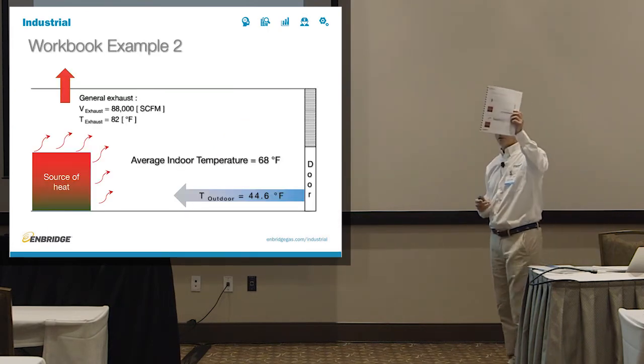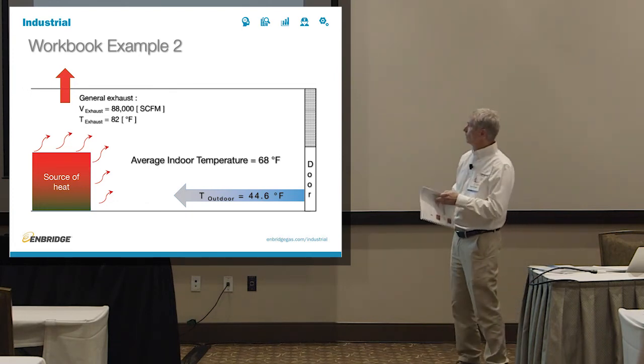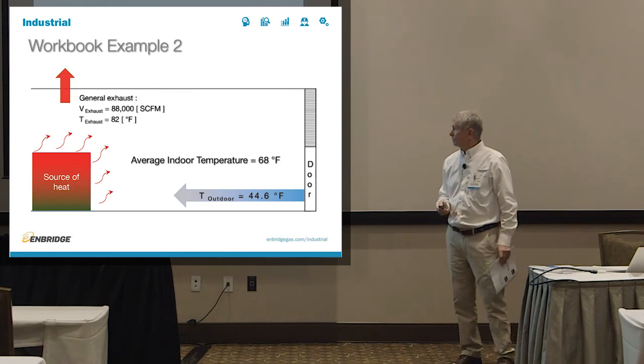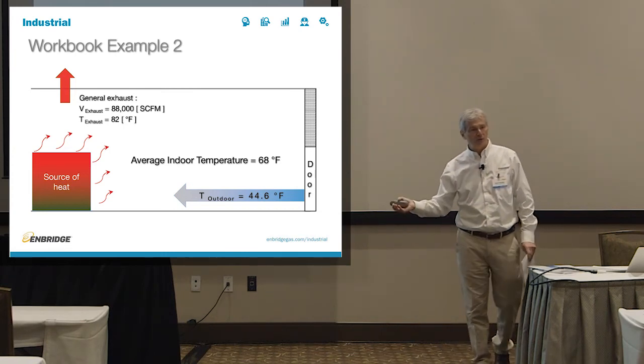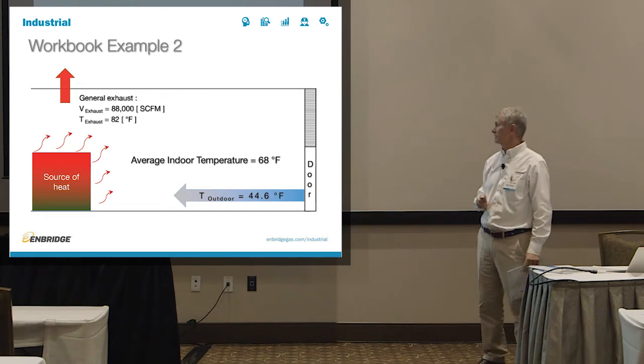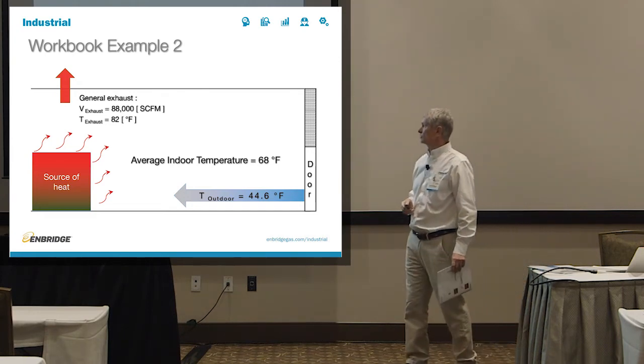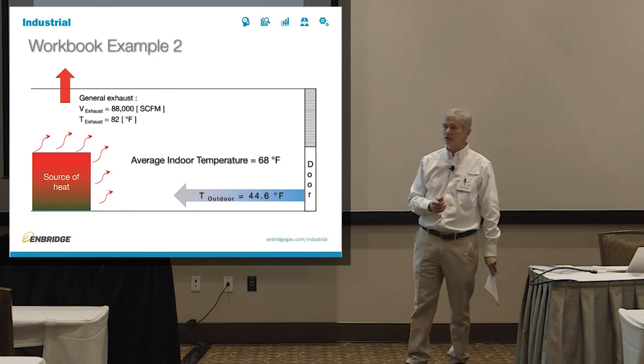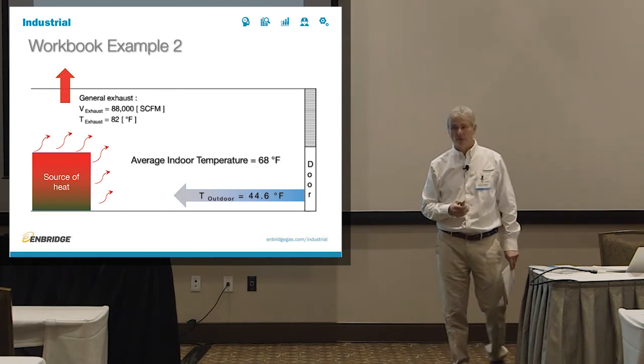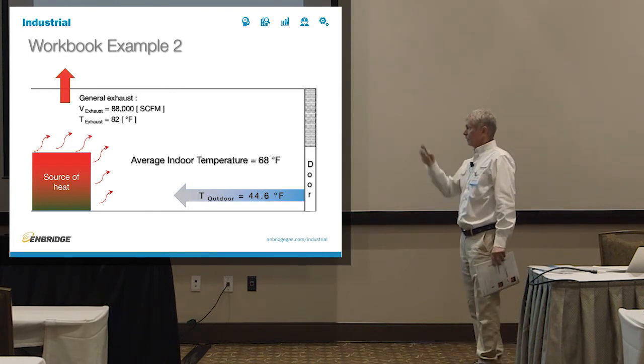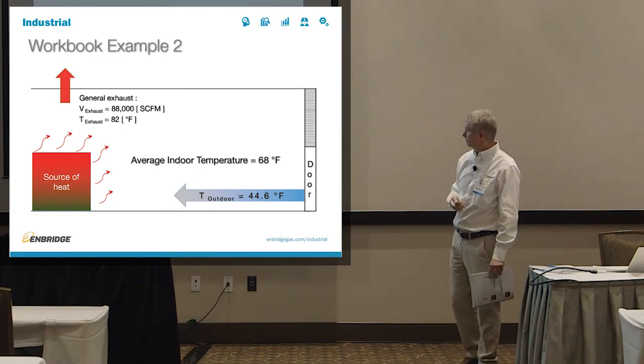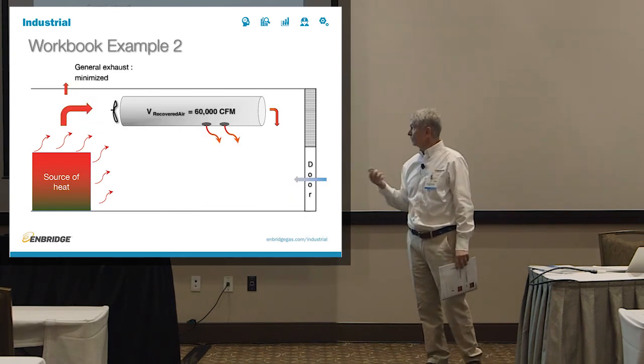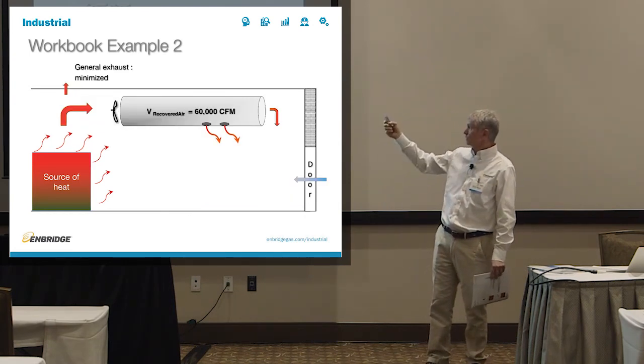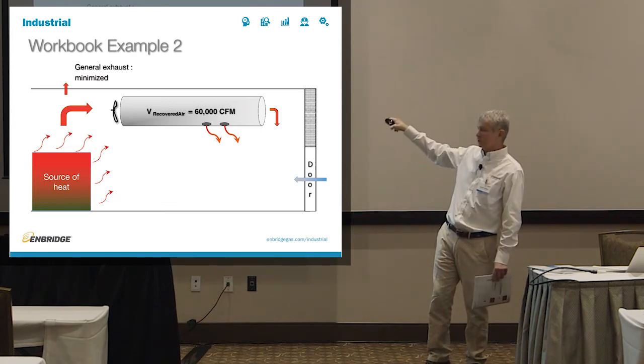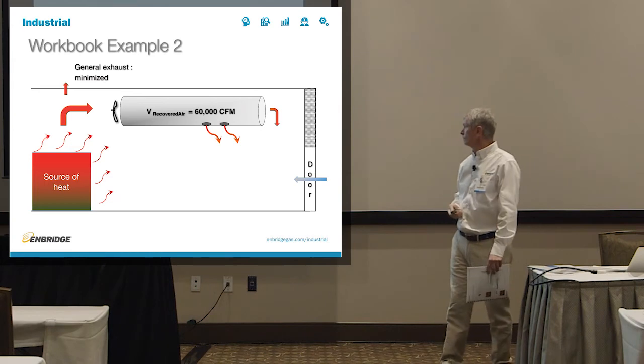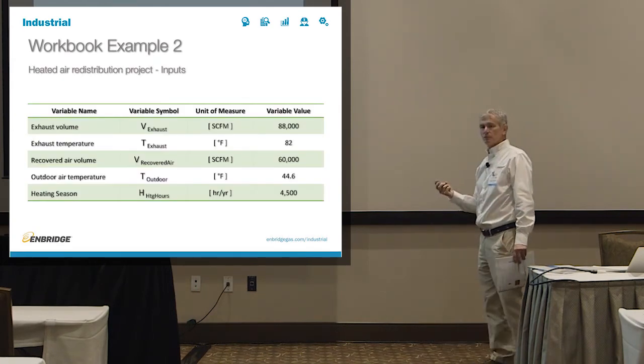So if you look at your workbook, this is the second one. We'll assume that the average outdoor temperature that comes into the facility is 44.6 degrees F. We'll say that we have a source of heat here and that we're exhausting 88,000 CFM of air at 82 degrees F out of the facility. We want to hit an average indoor temperature of 68 degrees F. We want to minimize the exhaust, and we want to put in fans that will move 60,000 CFM of air across to the shipping door area.